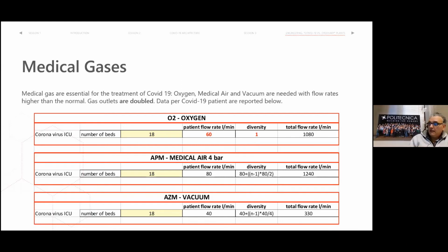On the other hand, for medical air and vacuum, we can apply a diversity. This is a diversity which is the proper one for intensive care units, and is taken from the British standard, the HTM 0201, which is often used even in Italy, to define the diversity. However, the single flow rate for the patient is quite high, and the total flow rate is even quite high.